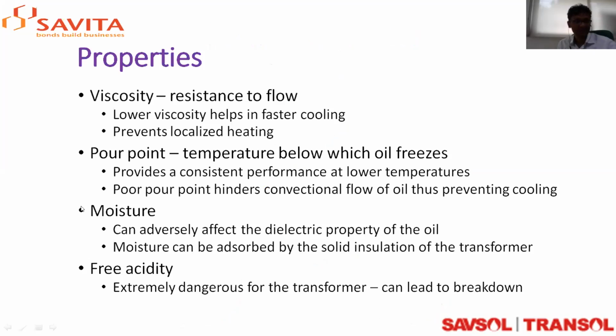Next one. As I briefly touched in my earlier slide, before starting I would like to add to Vaidya sir's point: the oil is the only component in the transformer which touches every part of the transformer. So it carries whatever is happening in each and every corner of the transformer. Whatever is forming, suppose heat is forming, the oil takes the heat. It doesn't allow current to flow from the coil, primary to secondary load, and it doesn't allow that to touch the tank. So the purpose of the oil is insulation. Let us come back to our properties section, that is viscosity of the oil.